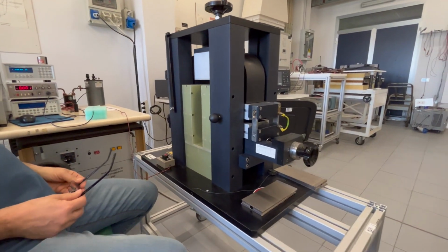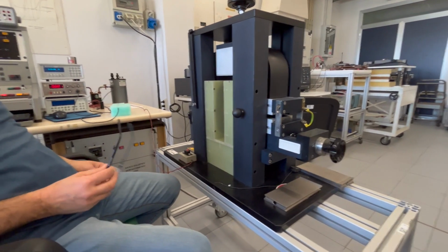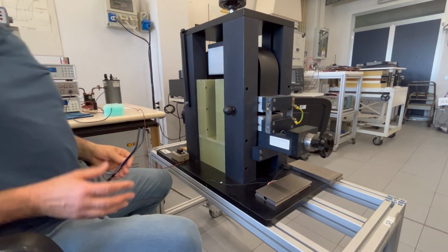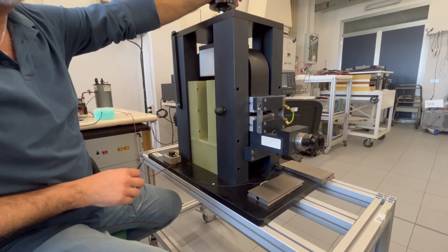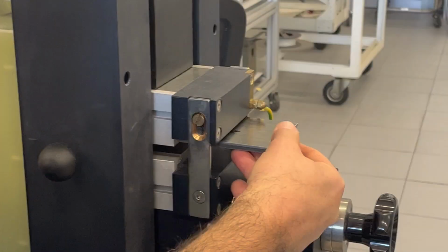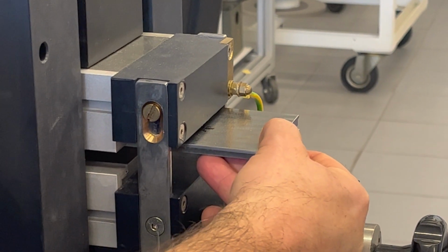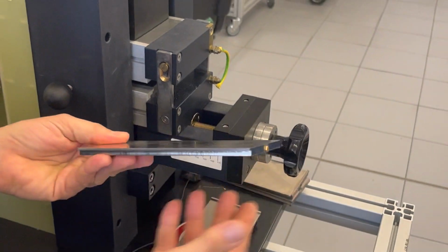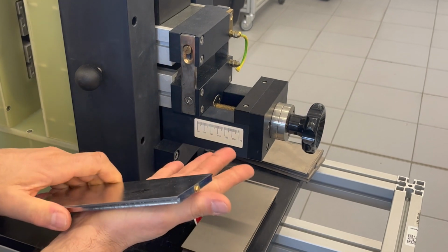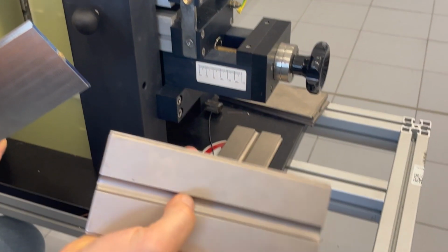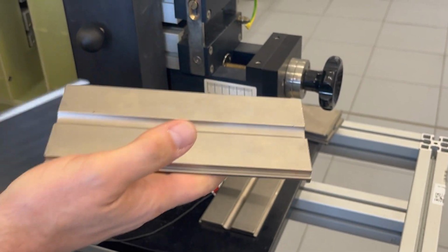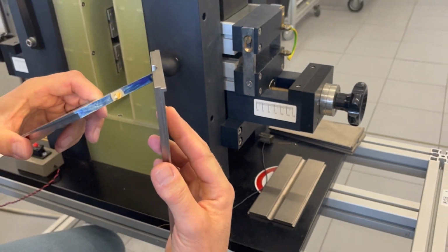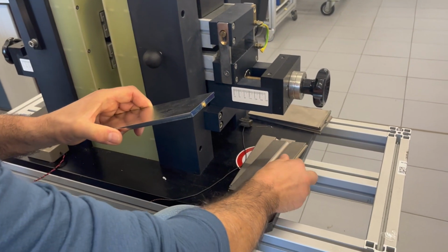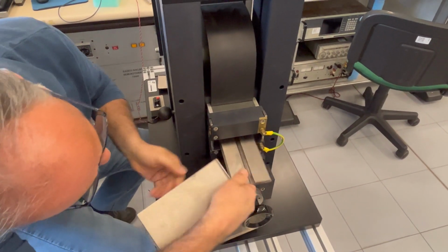The sample is now ready to be measured with a permeameter, which is an incomplete iron yoke. The sample will complete the closed magnetic path when it is inserted in the proper way into the permeameter. The ferromagnetic yoke is equipped with adapters that can accommodate samples of different shape. In particular, there are adapters for flat samples, such as sheets, and for cylindrical samples, such as the bar that we are measuring today. These adapters must be inserted in the proper position on the left and right of the yoke, so that the sample can be placed in the middle and can ensure a repeatable and efficient closure of the magnetic flux in the yoke.